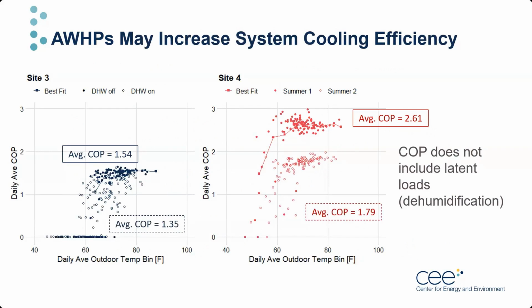So now one thing we haven't talked about yet is cooling. Here we have two charts, one for each of the monoblock sites, which are the only sites with cooling. Both charts show cooling performance curves with daily cooling COP on the y-axis and OAT on the x-axis. Note that these COPs do not include latent loads and so are based on sensible cooling only.